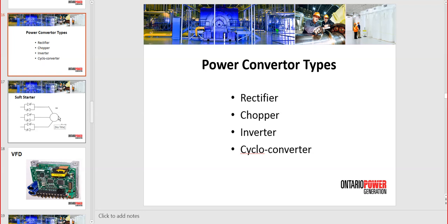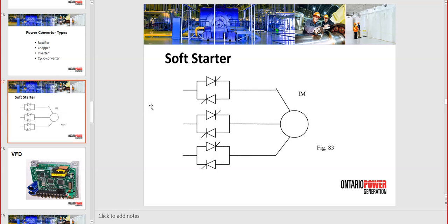Any questions on the 4 power converters? If not, I will jump to the soft starters. Now, don't be confused with starters. When we say motor starter, that is one thing; when we say soft starter, that is another. The motor starter, as we know it, is an electromechanical contactor, a breaker, overload, all that part that is in a box in an MCC starter. But when we say soft starter, this one is electronics.